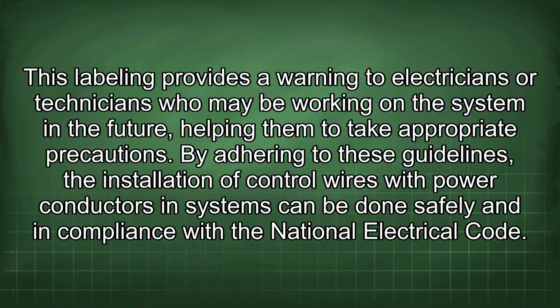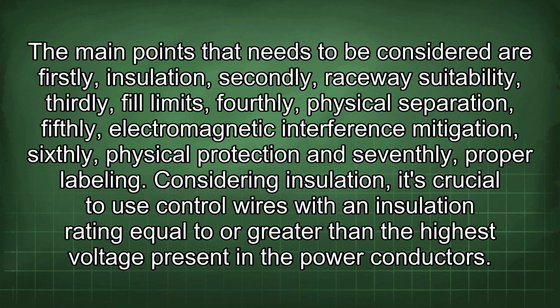By adhering to these guidelines, the installation of control wires with power conductors in systems can be done safely and in compliance with the National Electrical Code. The main points that need to be considered are, firstly, insulation; secondly, raceway suitability; thirdly, fill limits; fourthly, physical separation; fifthly, electromagnetic interference mitigation; sixthly, physical protection; and seventhly, proper labeling.